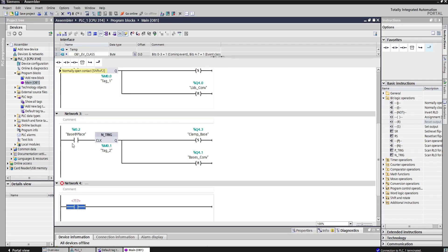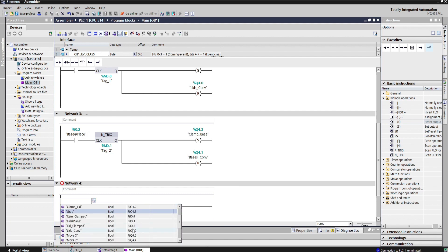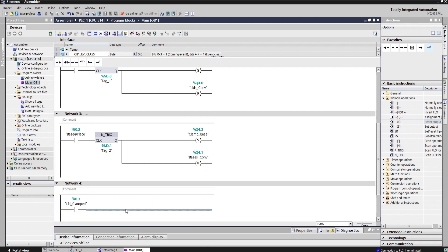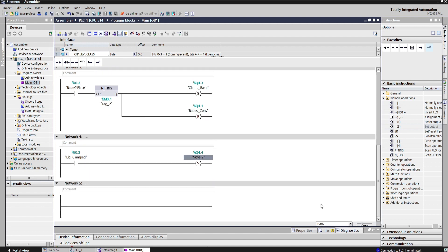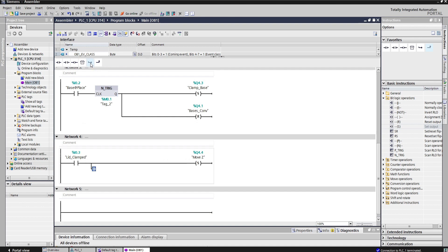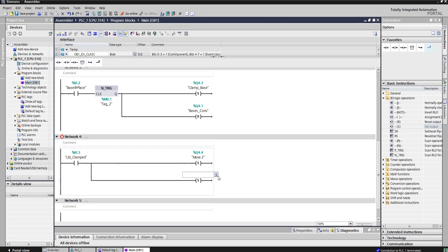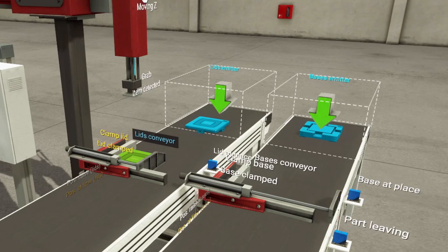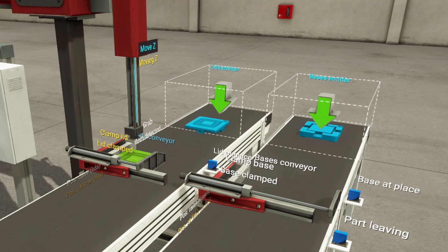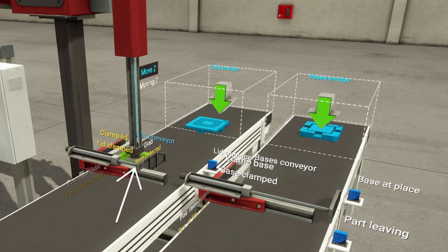For network 4, let's place a normally open contact for lid clamped. When lid clamped energizes, the mechanical arm will go down — so let's add a set function for move Z, and then another set function for grab. When the arm gets down to grab the product, the item detected function will energize. Item detected will reset the 3 functions set before and move the arm forward to the base conveyor.